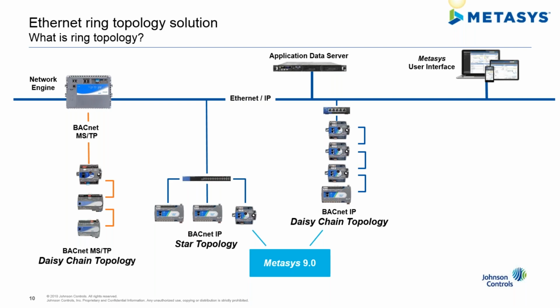Star topology is much more resilient to a cable failure, so that if a single cable between a switch and a controller were to break, the network engine could still communicate with the downstream controllers. The problem with star topology is that it's more expensive from an installation cost perspective. It requires more ports on the switch and more length of cabling as the Ethernet is home run from the controller to the switch. Now daisy chain topology is less expensive to install because the cabling is daisy chained from one controller to another, and it also requires significantly fewer switch ports.